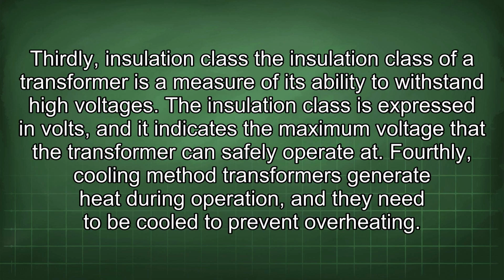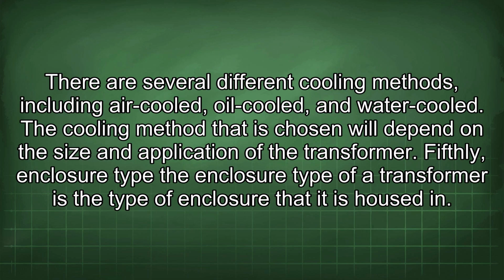Thirdly, insulation class. The insulation class of a transformer is a measure of its ability to withstand high voltages. The insulation class is expressed in volts, and it indicates the maximum voltage that the transformer can safely operate at. Fourthly, cooling method. Transformers generate heat during operation, and they need to be cooled to prevent overheating. There are several different cooling methods, including air-cooled, oil-cooled, and water-cooled. The cooling method that is chosen will depend on the size and application of the transformer.